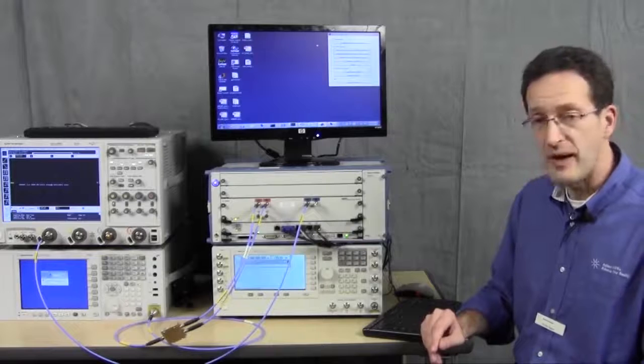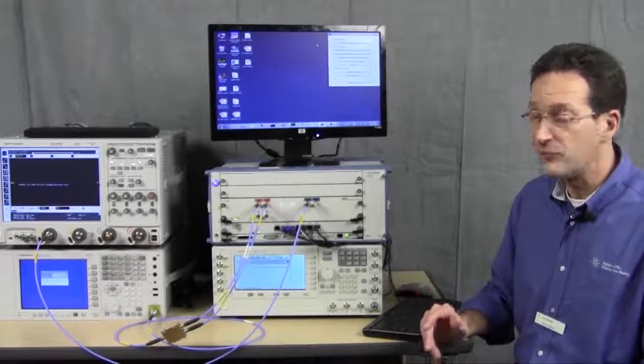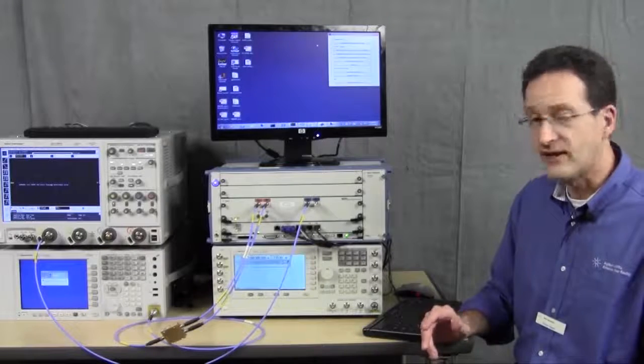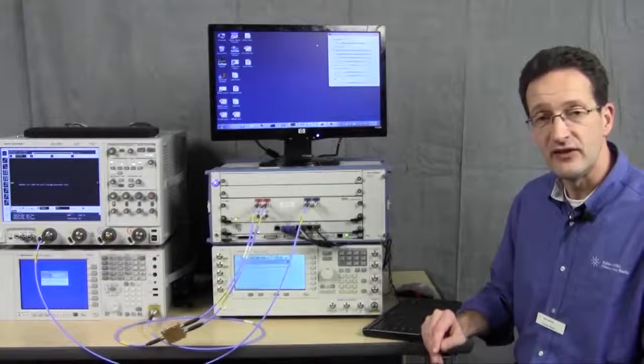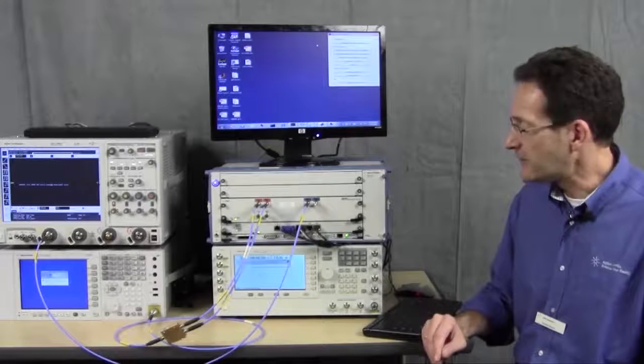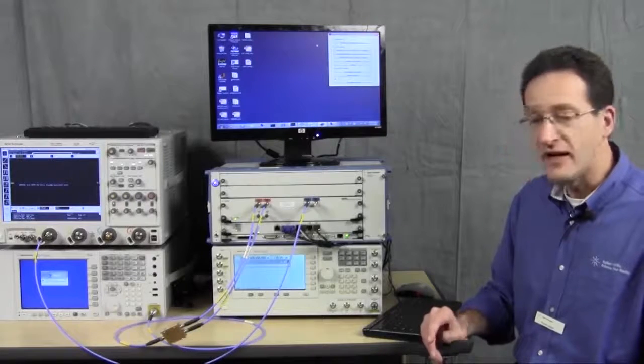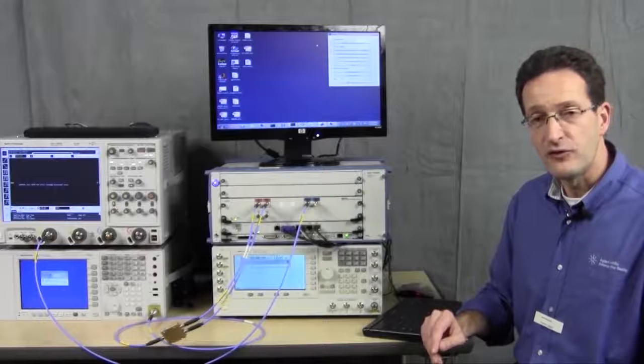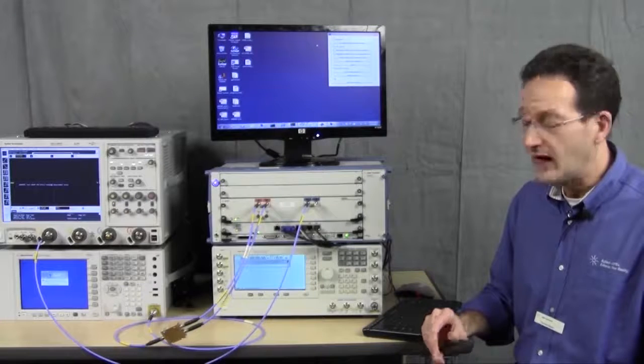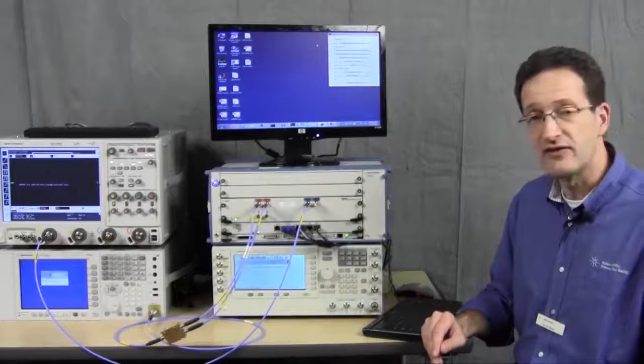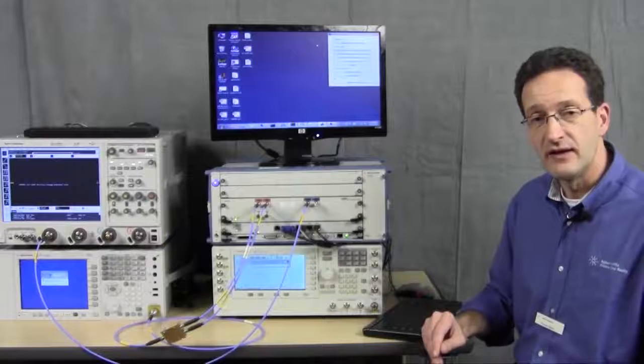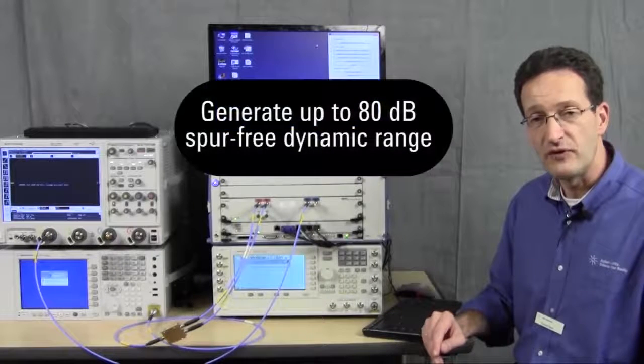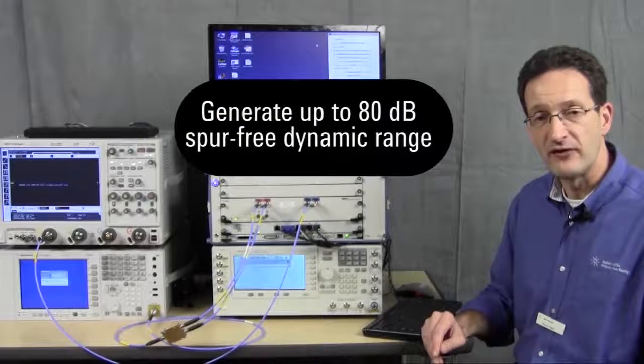With signal bandwidth getting wider and wider, it is important to have high fidelity signals at high bandwidth being generated. With the M8190 and up to 14-bit vertical resolution, up to 8 gigasamples per second sample rate, it can generate signals with up to 80 dB spur-free dynamic range.